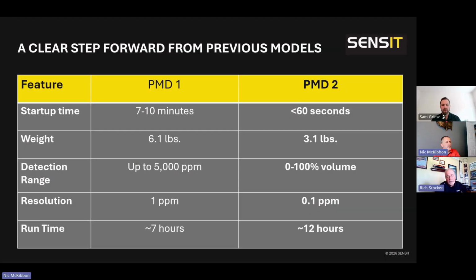As we talk about this, Nick's going to fire up a video showing everybody in real time what it takes to start this instrument and get it running. Our startup time on the old PMD1, which used infrared technology, could be anywhere from 7 to 10 minutes if the instrument was in ambient 70-degree temperature, and it may take longer than that. You're generally under 60 seconds on the PMD2.